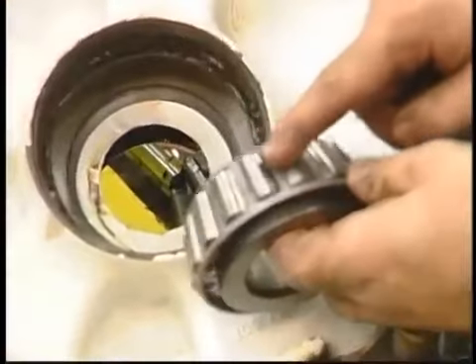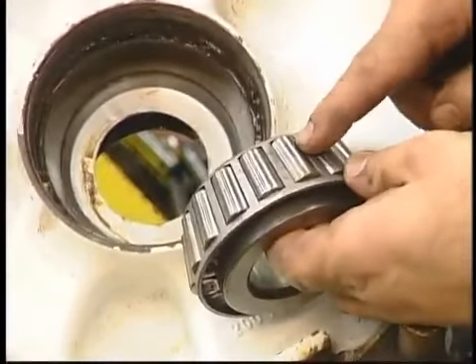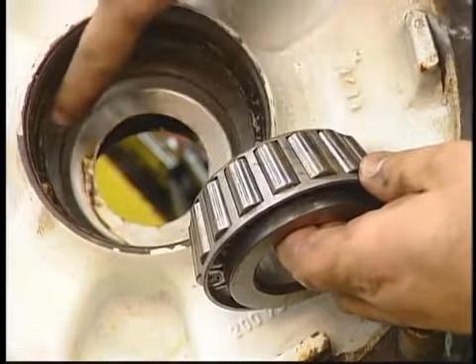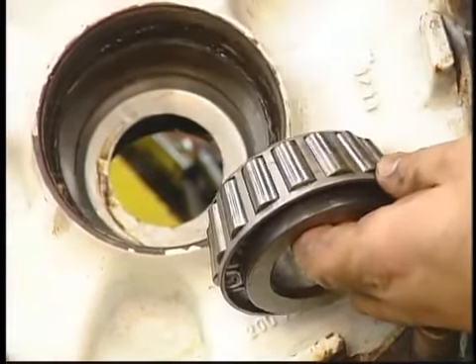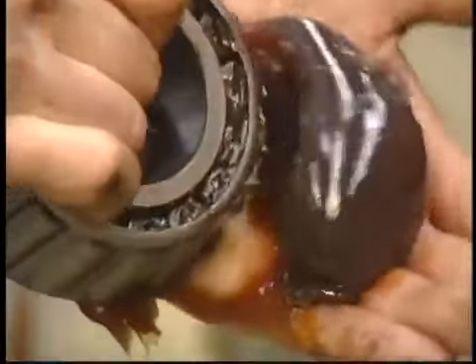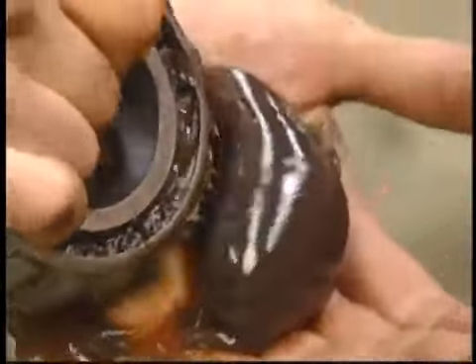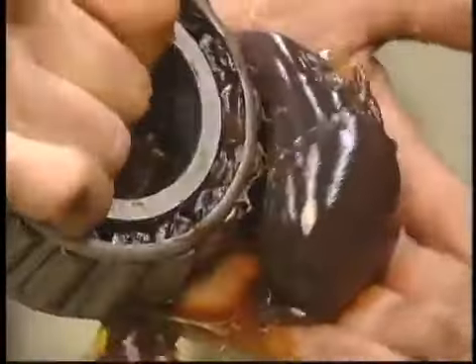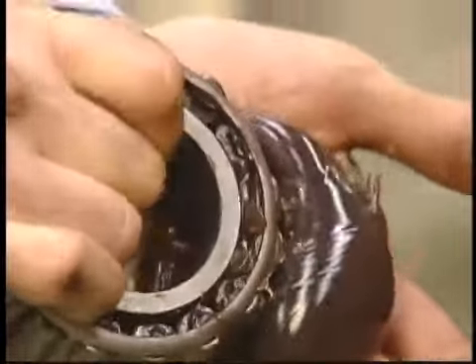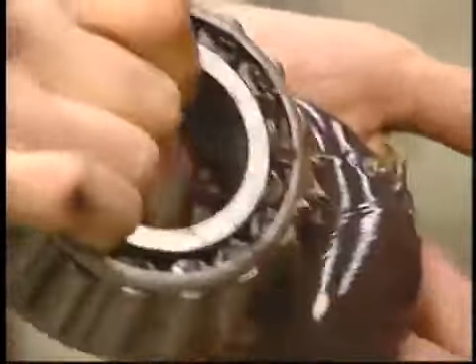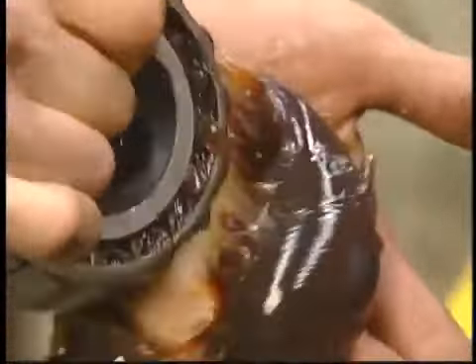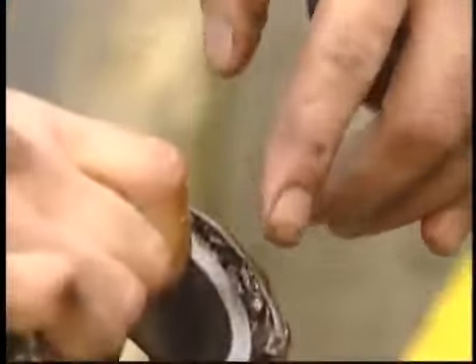Inspect the bearing and races for signs of wear, overheating, and pitting. Ensure that the grease slinger is not damaged. Pack the bearings thoroughly with grease. See it coming out? The grease should be forced all the way through the bearing cage.